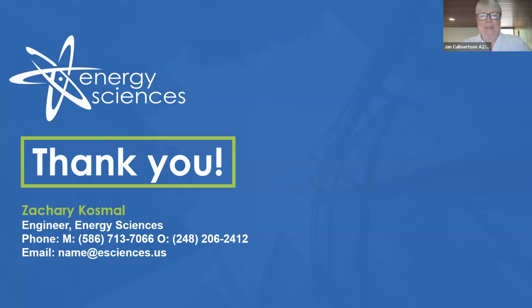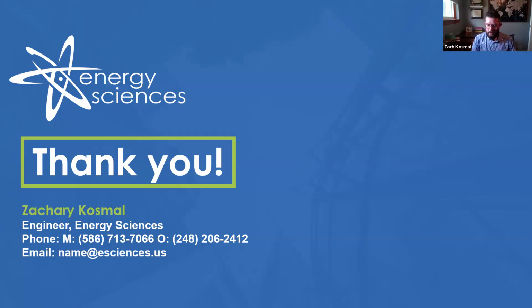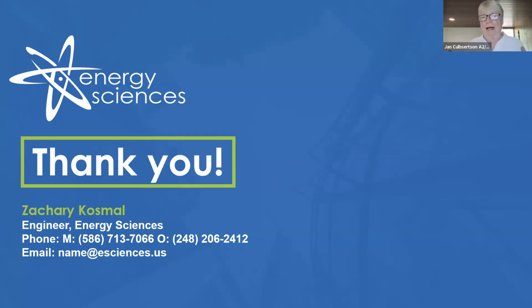So we do have several questions. How does this presentation apply to residential systems? Good question. I did make this presentation mainly for commercial applications, but pretty much anytime I mention a split system air source heat pump, that can typically be used in a residential application. Those mini split systems, the air source heat pumps, are typically common residential applications as well. So I hope that answered that question. A lot of the efficiency ratings and all of that apply, no matter what. Good point. Exactly.